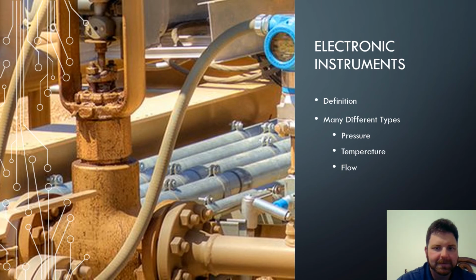Temperature could be the same thing. However, it wouldn't be a valve for temperature. It'd probably be some kind of heating system. And flow, that actually might use a valve, so to control flow, it might pinch back or something like that. So as an electrical technician, you have to be able to troubleshoot, repair, and calibrate these. Let me go through a little bit of the process of doing so.